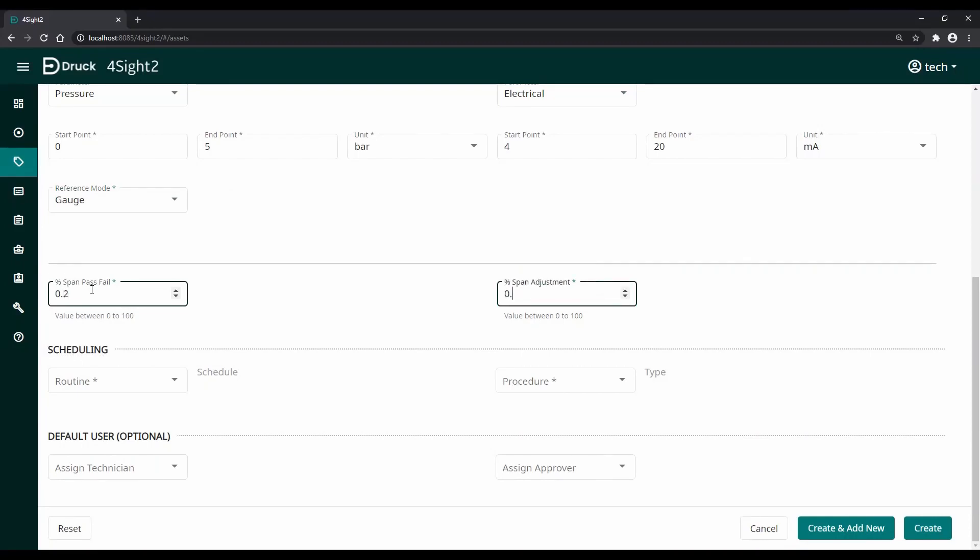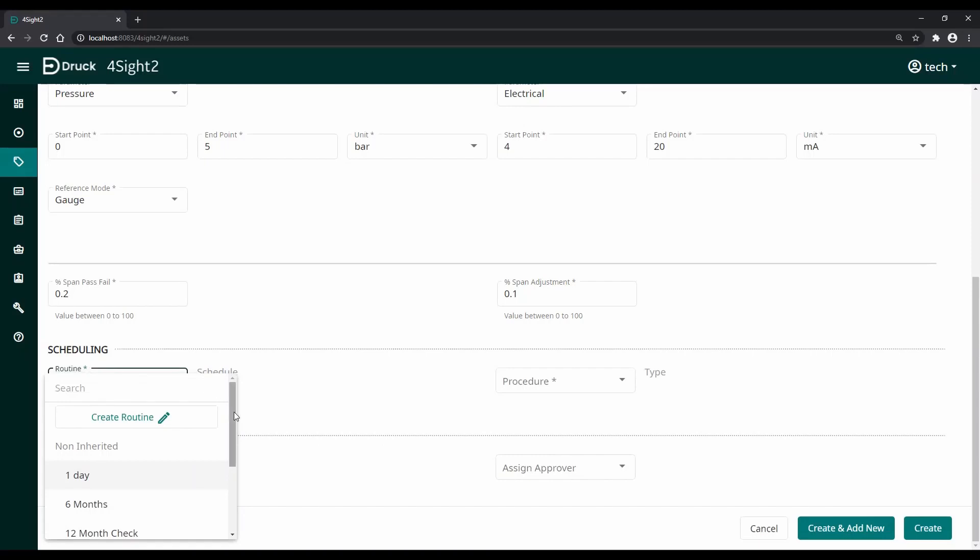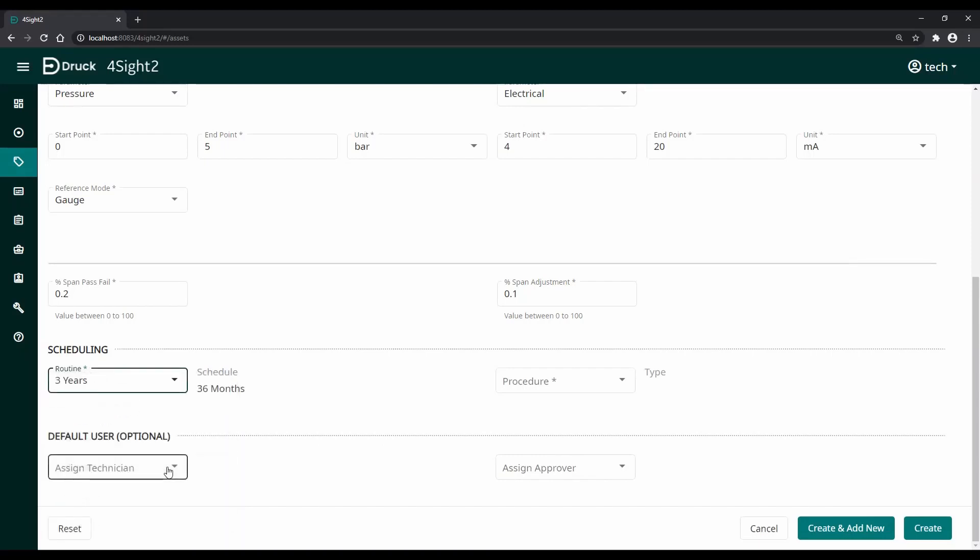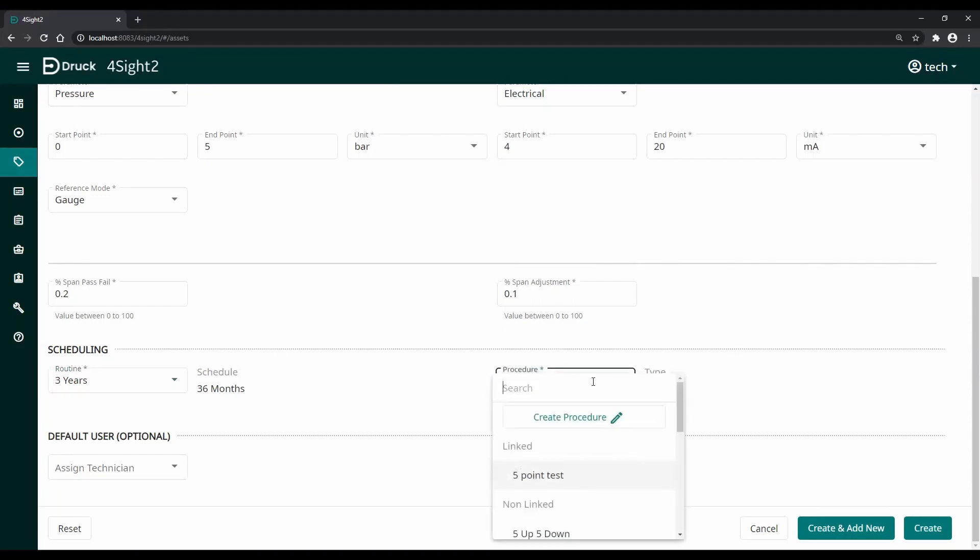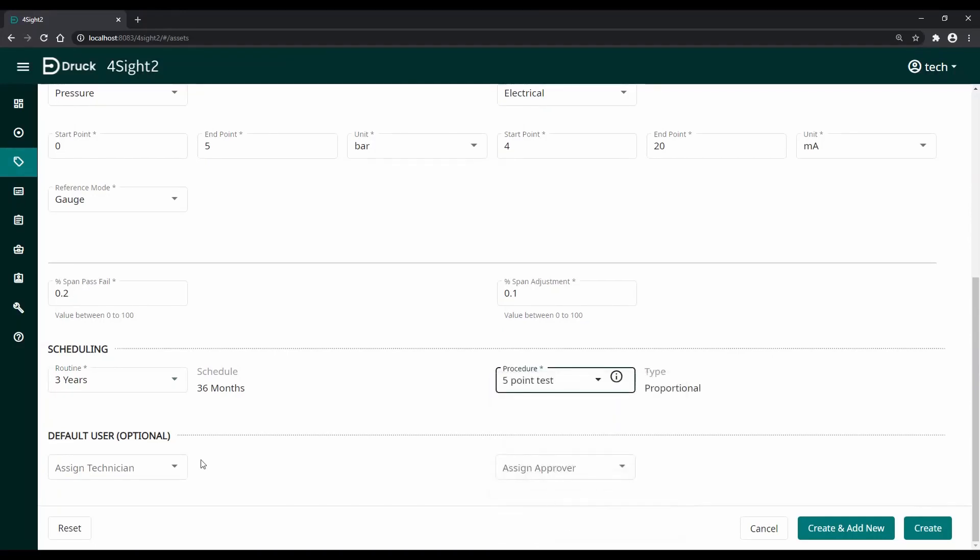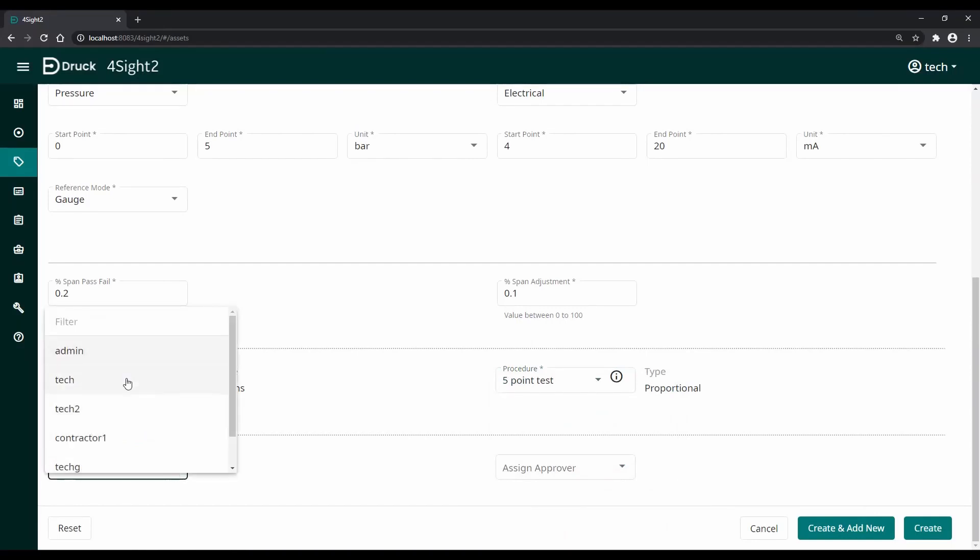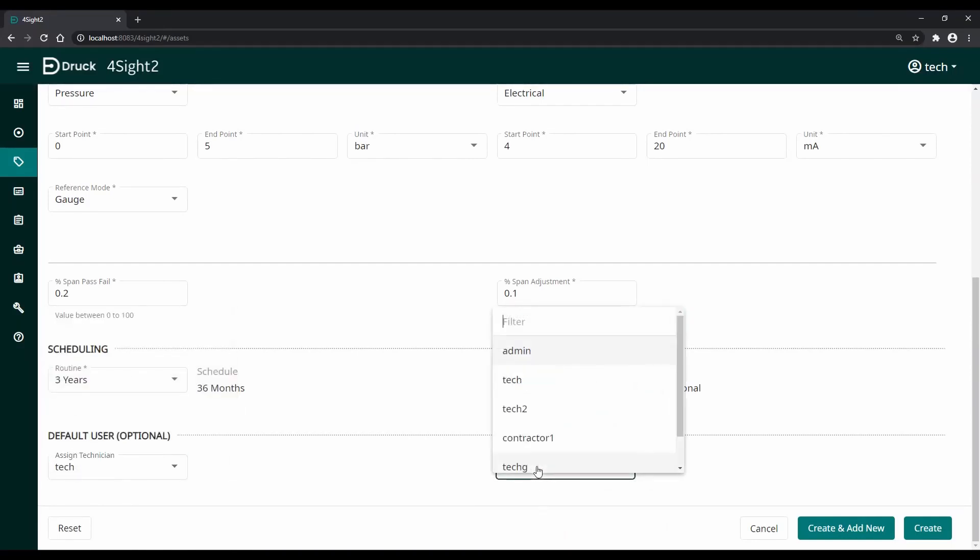You can add two tolerances in 4Sight2 which is our pass fail span and your adjustment span, and finally we'll assign a calibration routine and a calibration procedure. You can optionally assign a technician and a supervisor if you wish.